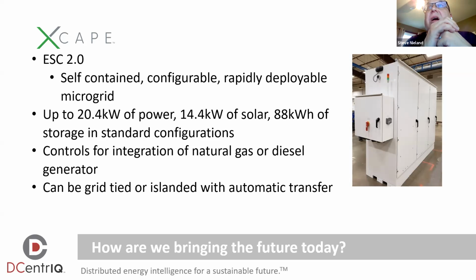This unit is also designed to be plug and play, so it's rapidly deployable. I can set it in place on a site, put in 2 pre-assembled ground mount solar arrays, plug those in with quick disconnects to the cabinet, set a small 20 kilowatt generator on site, plug that in also, and then terminate out to my loads. I can have this whole system up and running in less than half a day with 2 people.